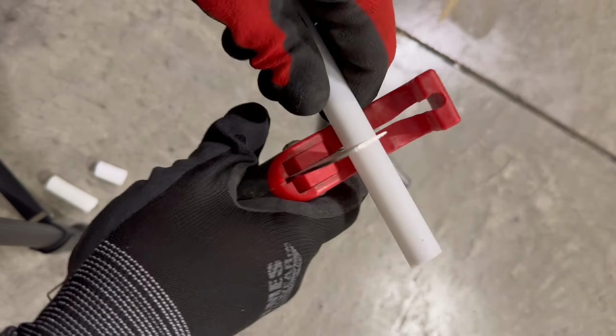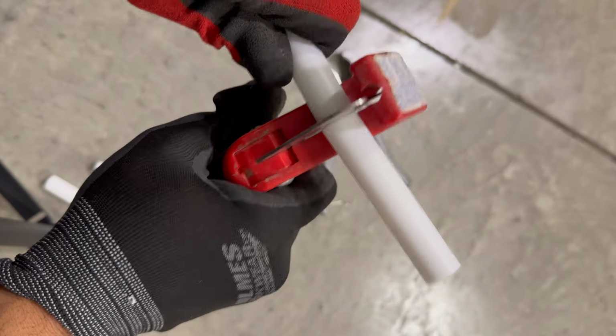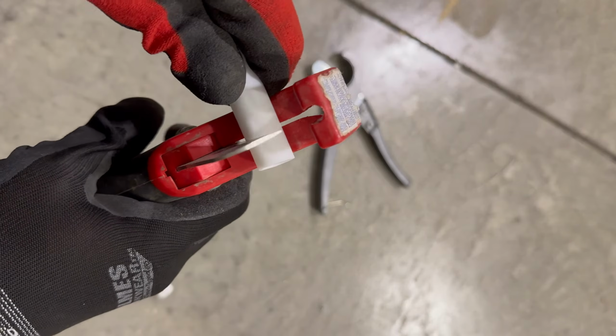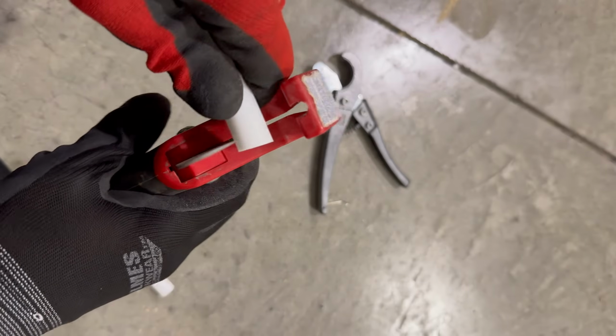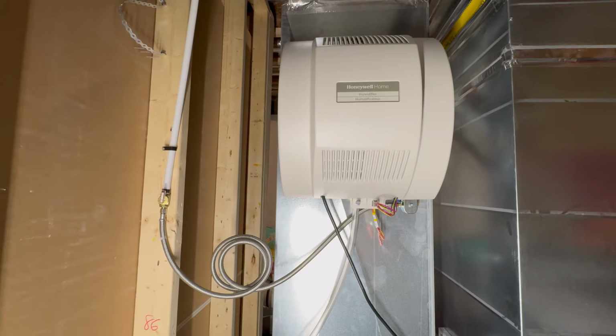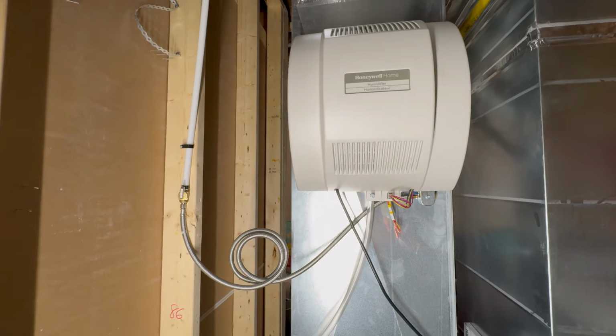Now, you need to install a water line to your humidifier. I cannot guide you as to the best option for you. Some of you may have PEX, others may have copper. Complete the installation with the 1/4-inch braided water line. Do not use the included saddle valve and plastic water line. They are not reliable. So as I mentioned previously, I won't be using the saddle valve.